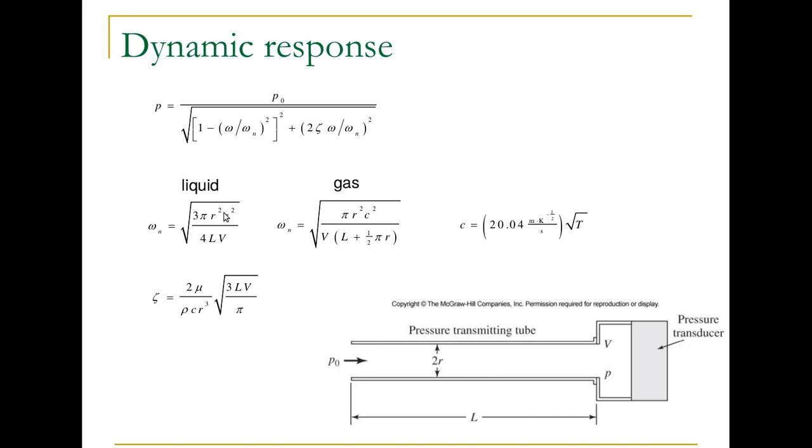The natural frequency depends on the geometry, so the radius of the tube, the length of the tube, and the volume here that's in contact with the transducer. It also depends on the speed of sound in that fluid, so that's given by this expression.